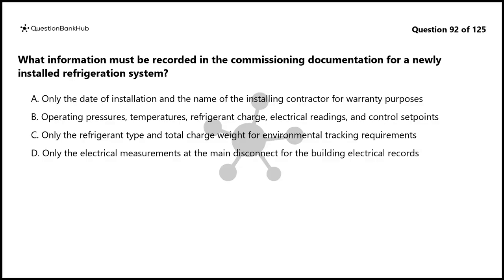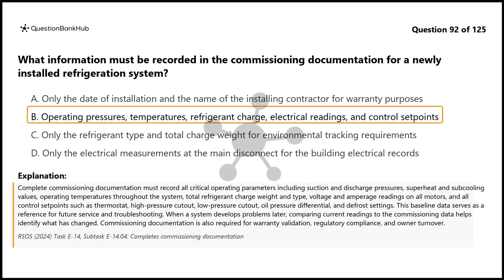The correct answer is B. Complete commissioning documentation must record all critical operating parameters including suction and discharge pressures, superheat and subcooling values, operating temperatures throughout the system, total refrigerant charge weight and type, voltage and amperage readings on all motors, and all control setpoints such as thermostat, high pressure cutout, low pressure cutout, oil pressure differential, and defrost settings.